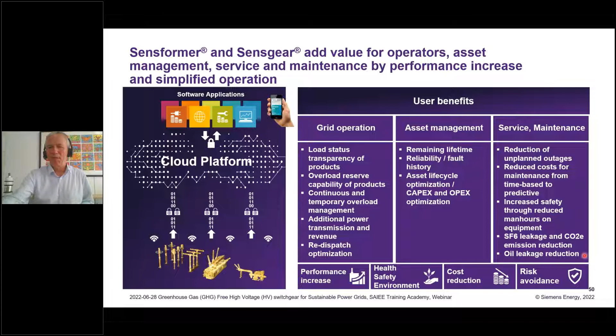For service and maintenance, you have a reduction of unplanned outages. You see early the status of your products. You have reduced costs due to the fact that you don't do time-based maintenance, but go into predictive maintenance. You see a failure coming before it happens. You have increased safety because you don't need to go to the equipment to see its status - the status is sent to you through an app. In case of SF6 topics, you get an early indication of leakage before you usually have the warning and the alarm - you see that earlier. And if you apply that to oil, you also see oil leakages early. So those are the benefits of that technology.